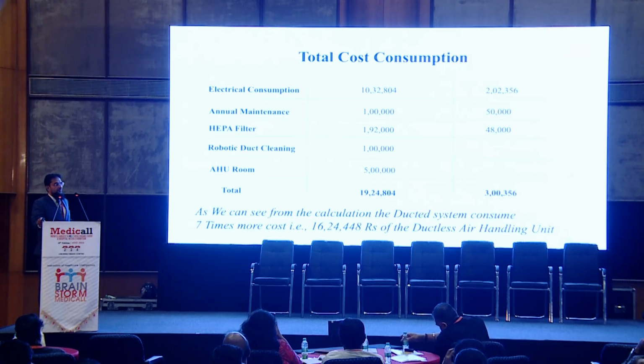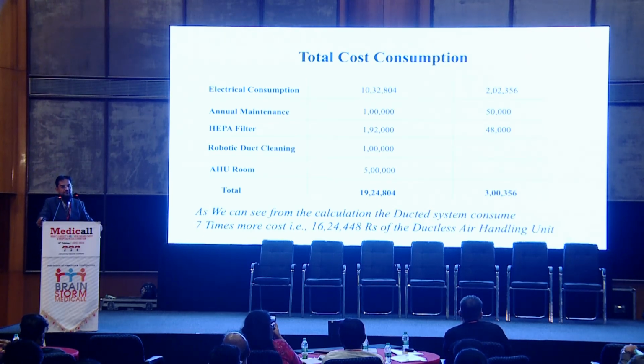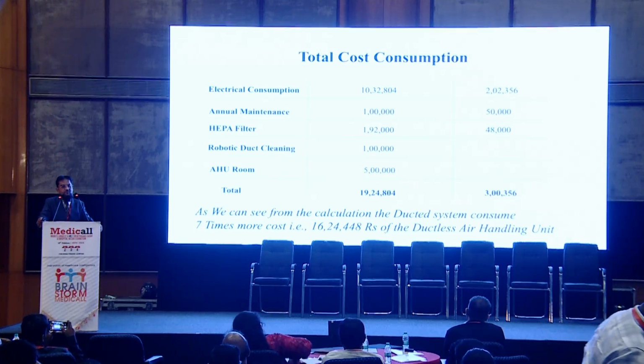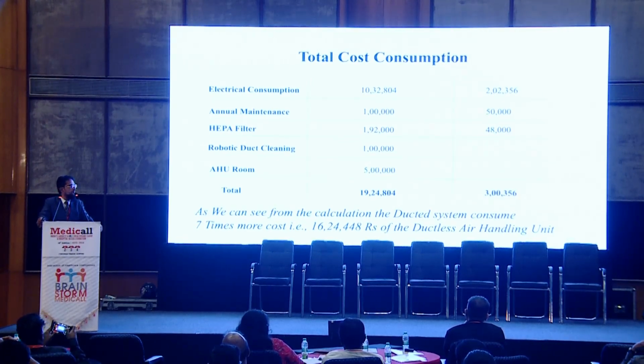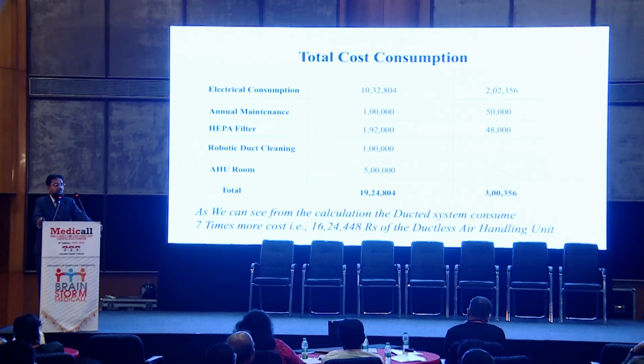Then from the maintenance point of view, ducted systems and AHU require more maintenance cost. AMC, CMC cost is also very high, goes up to 1 lakh rupees. In this, I had calculated just 50,000 rupees. Then you have to change your HEPA every 6 months, and validate your HEPA every 6 months. Here my HEPA has to be changed once in 2 or 2.5 years. And whether the HEPA is working properly or not, you will get on a display. We had given the display of the temperature, humidity, HEPA status.